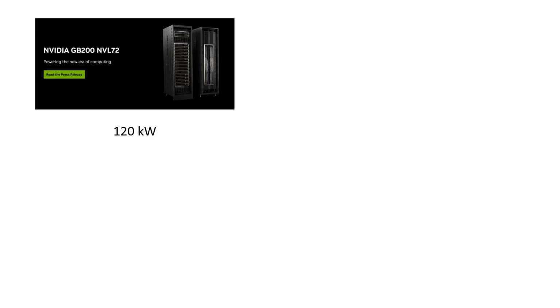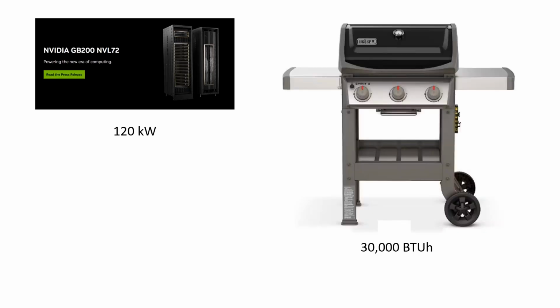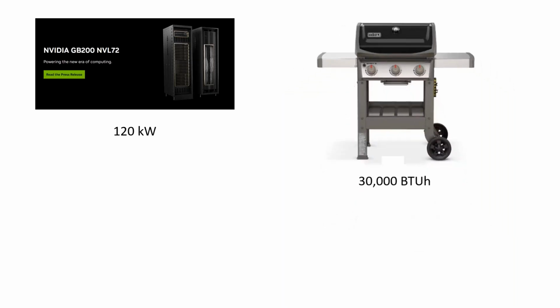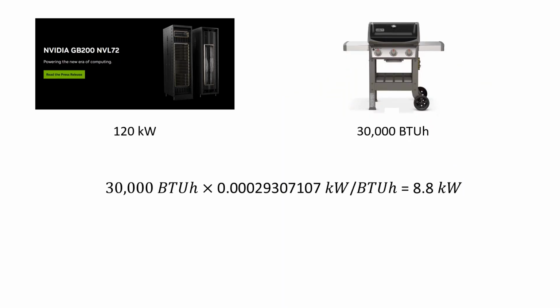Let's talk about 120 kilowatts per rack. Do you know how much heat this is? All right, let's take this as an example. This Weber 3-burner grill is rated at 30,000 BTUH, so we can cook a steak on there, we can cook our afternoon or weekend meals on there. What is 30,000 BTUH? Well, a little math tells us that's 8.8 kilowatts. That means there's roughly the heat equivalent of 13 and a half of these grills coming out of that server rack.